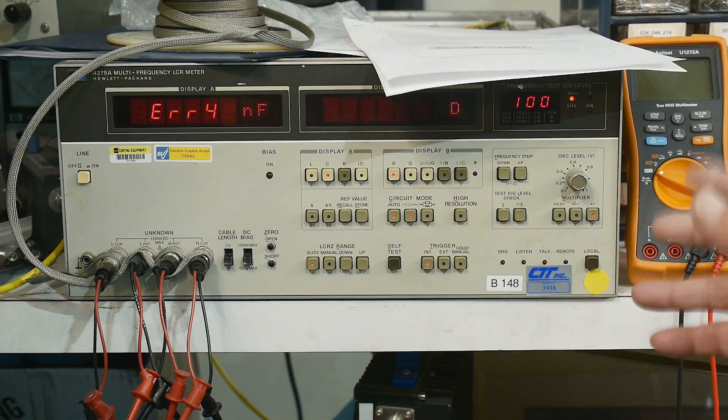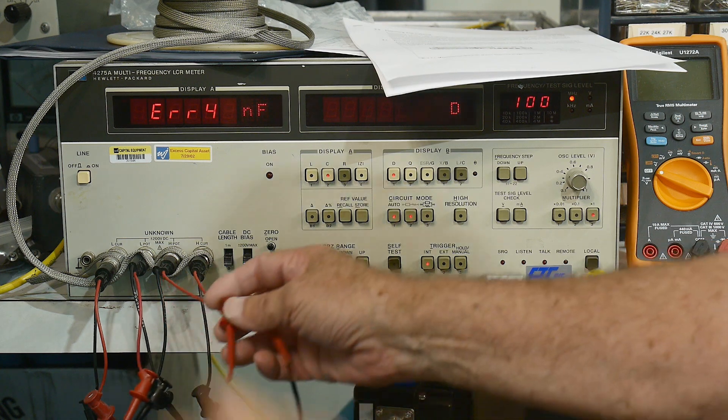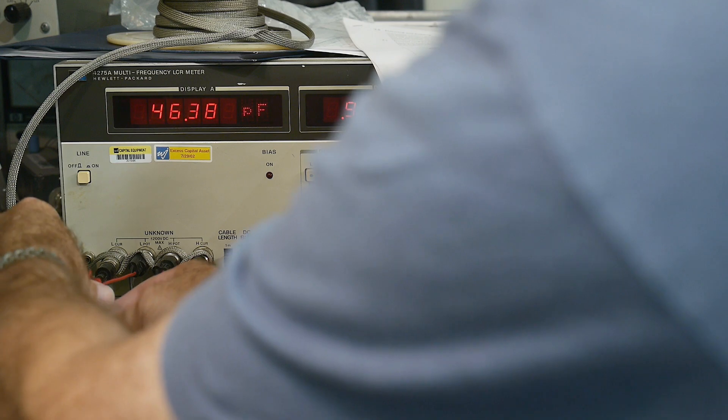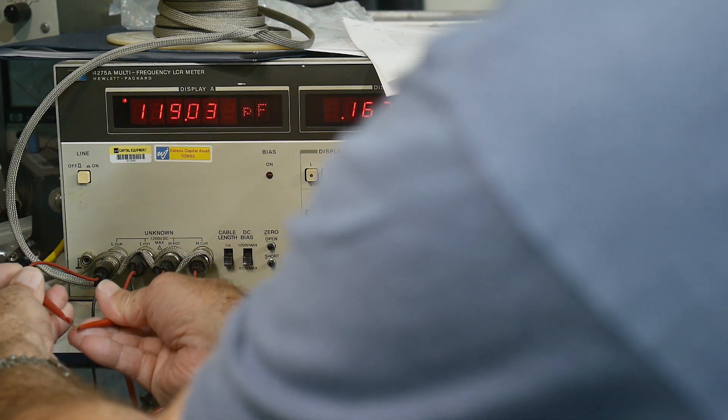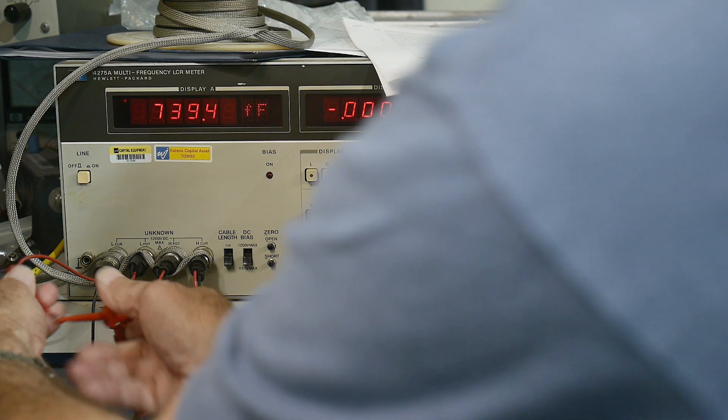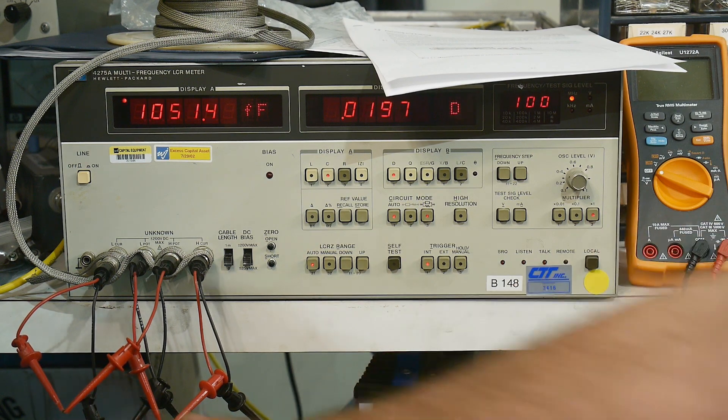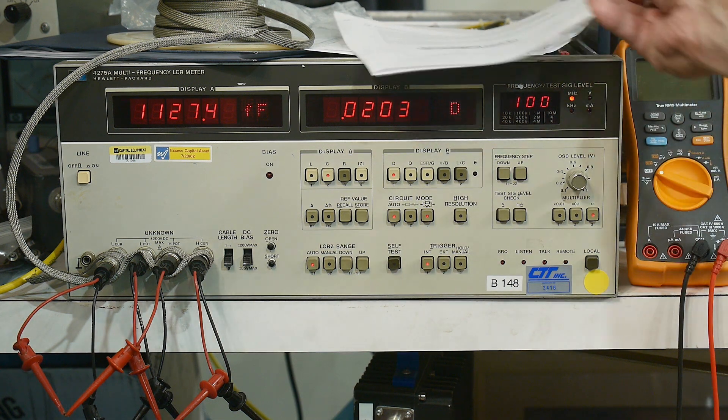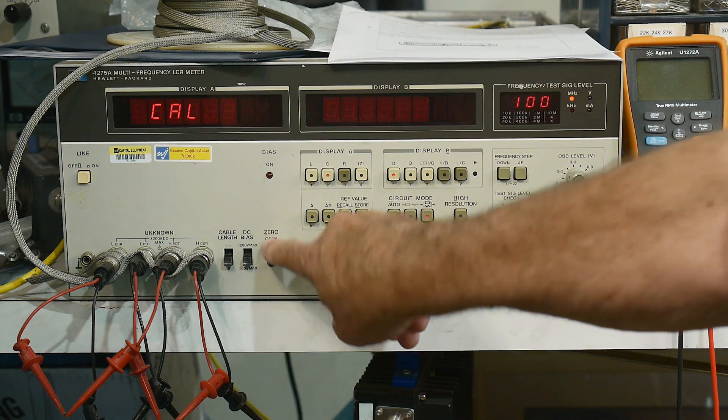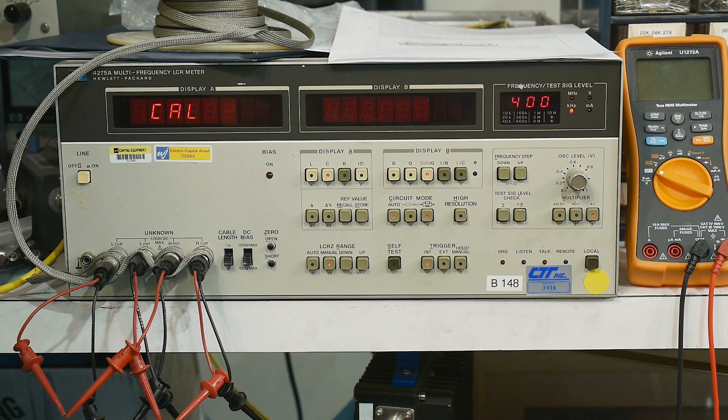The way these things work is it is still Kelvin, so you have a source and a sense and a source and a sense, and then you'll put the device between the two. When there's no device between the two, that's an open condition. If I hit the open, it actually will now complete the calibration. Before it wasn't, but now it actually completed the calibration.